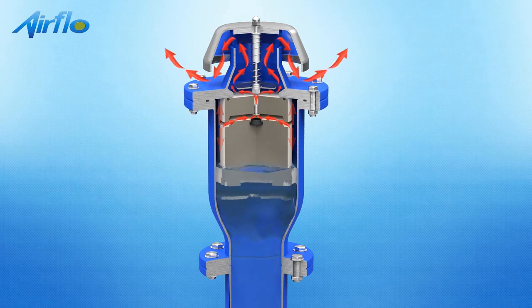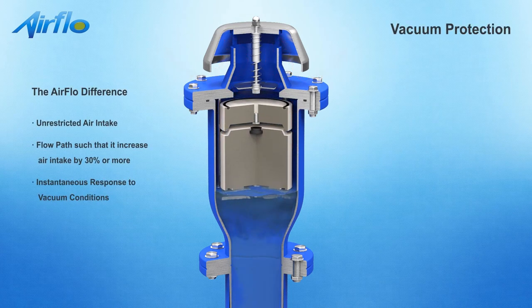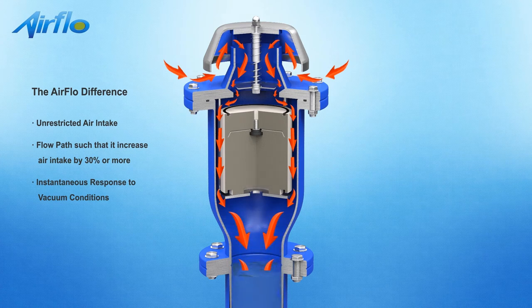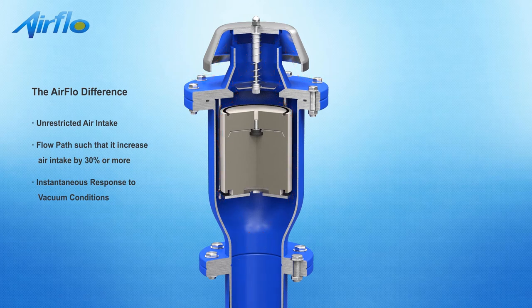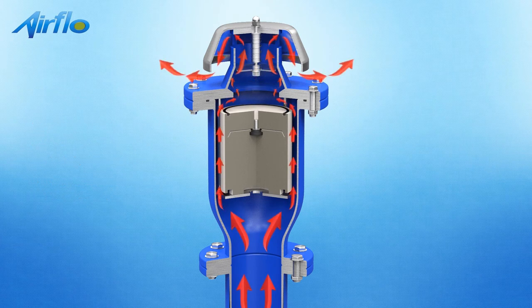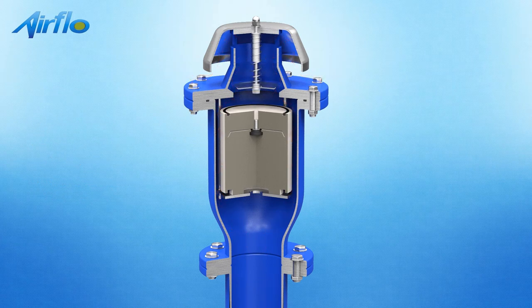Drainage of liquid from the valve causes the floats to move downwards onto the baffle plate assembly. This allows atmospheric air to flow through the valve and to rapidly displace the draining water in the pipeline, thereby preventing potentially damaging internal vacuum conditions. The flow path through the Airflo air valve provides up to 30% better vacuum protection in comparison to conventional designs of the same nominal diameter.